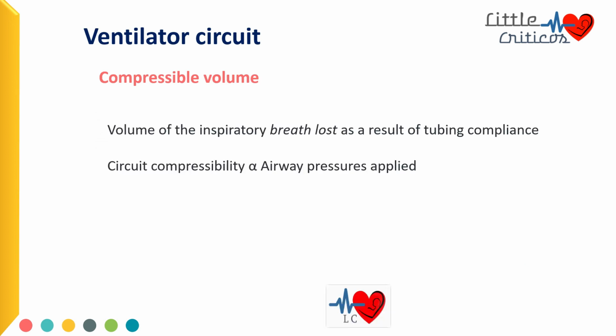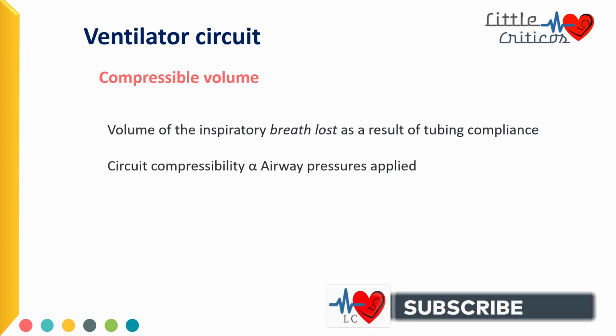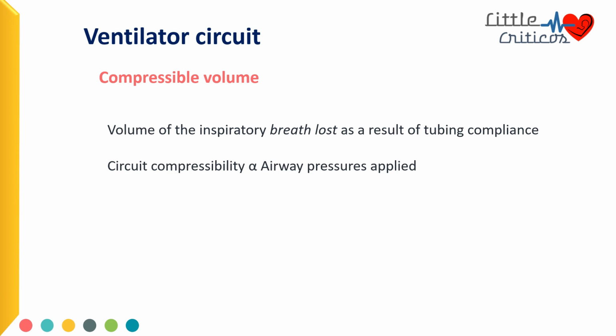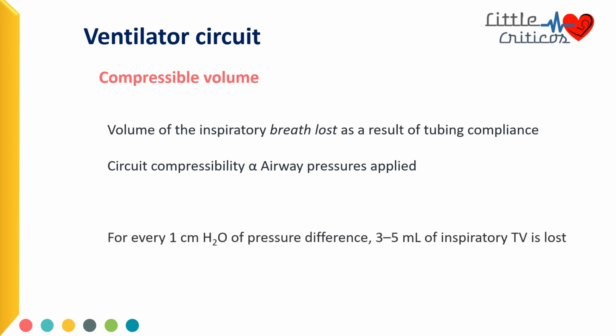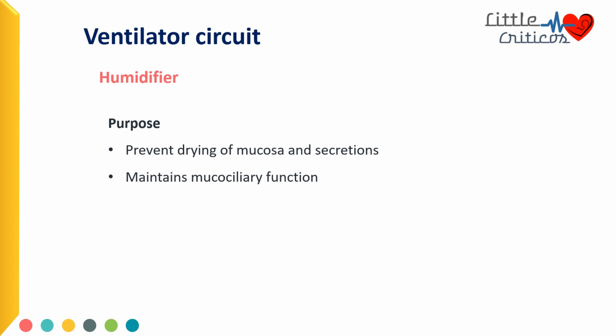Compressible volume is the term used to denote the volume of inspired breath lost as a result of tubing compliance. Circuit compressibility is directly proportional to the airway pressure applied. For every 1 cm increase in pressure difference, 3 to 5 ml of inspiratory tidal volume is lost in the circuit. Most ventilators self-adjust for this loss and it is not shown as tidal volume loss.